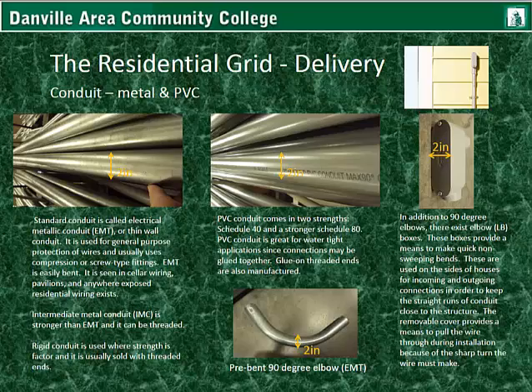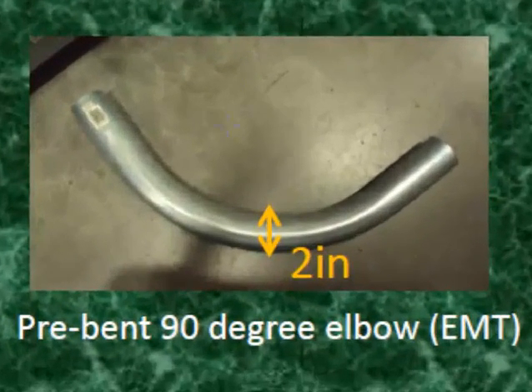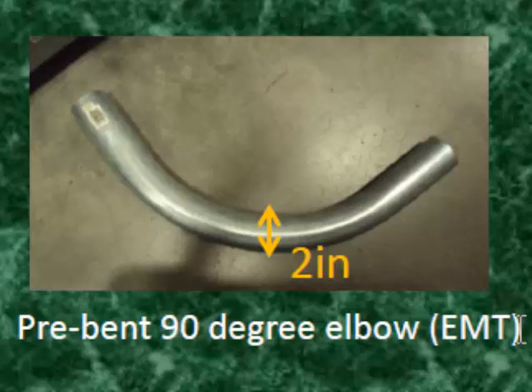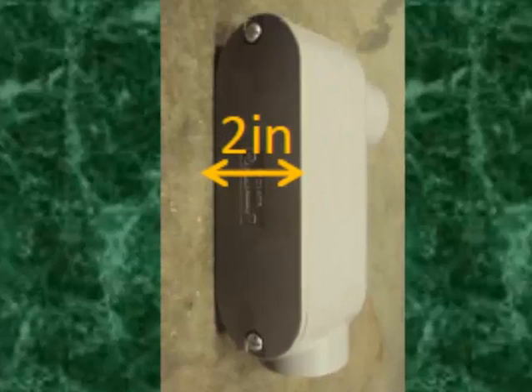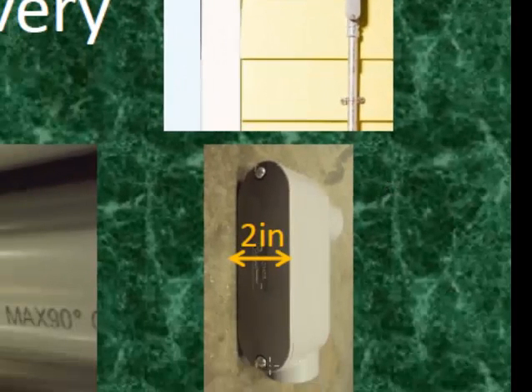At the bottom there's a pre-bent 90 degree elbow. In addition to 90 degree elbows, there also exist LB boxes. These boxes provide a means to make quick, non-sweeping bends. These are used on the sides of houses and buildings for incoming and outgoing connections in order to keep the straight runs of conduit close to the structure. The cover provides a means to pull the wire through during installation because of the sharp turn the wire must make — you can remove this cover, pull it out, and push it through.